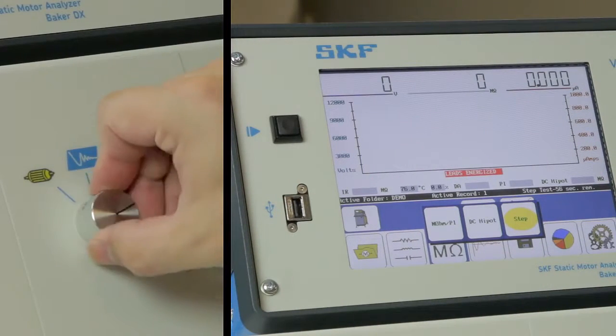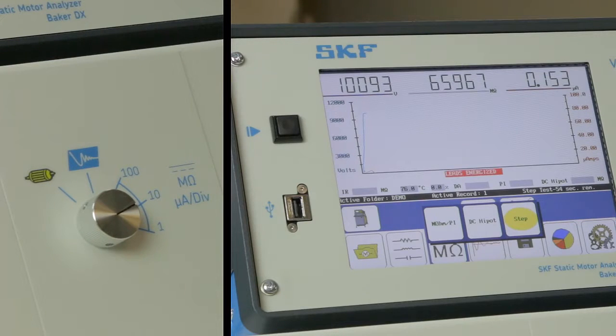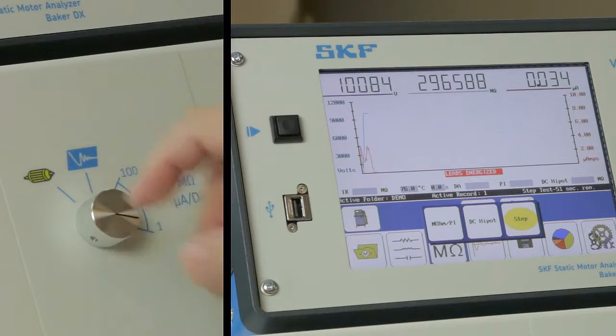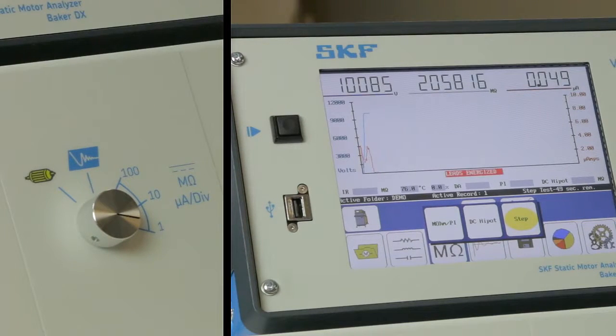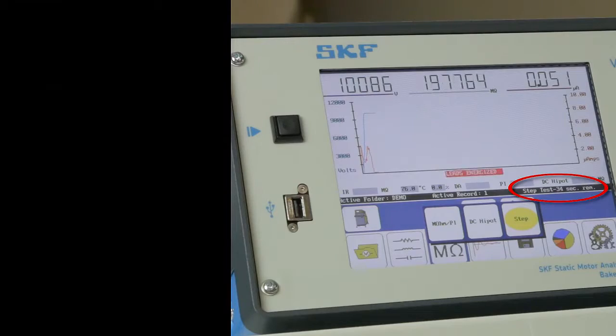While the voltage is held at a constant value, the leakage current will diminish over time. If the current value falls below half of the lowest division, turn the power pack's function knob to 10 microamps per division. The leakage current will continue to diminish, and if it again falls below half of the lowest division, turn the power pack's function knob to 1 microamp per division. Watch the seconds remaining countdown.